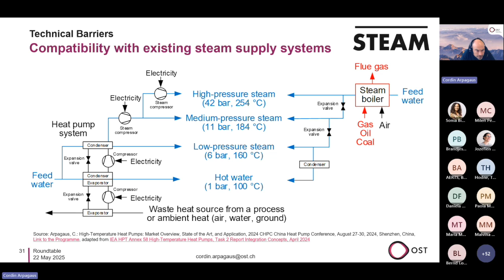When we change to heat pump technology, there is a mind shift, a different approach. We come up from the bottom, from the lower temperature, upgrading the waste heat with compression technology, mainly electrically driven compressors, generating hot water, then low pressure steam, and so on. It's a different approach to feeding these steam networks, which makes the integration complex.